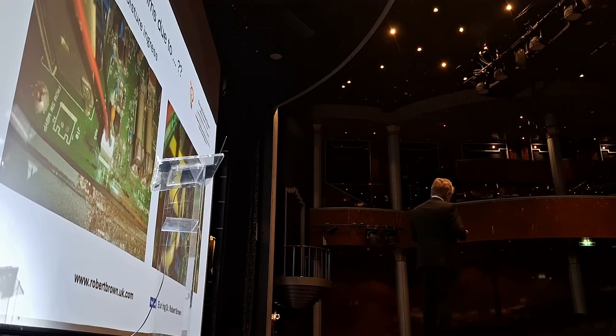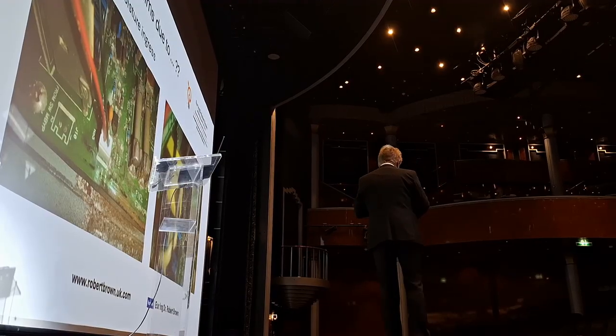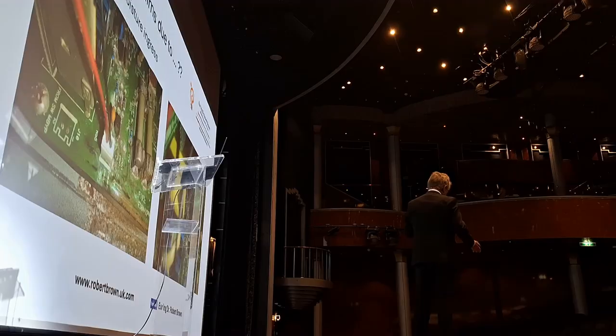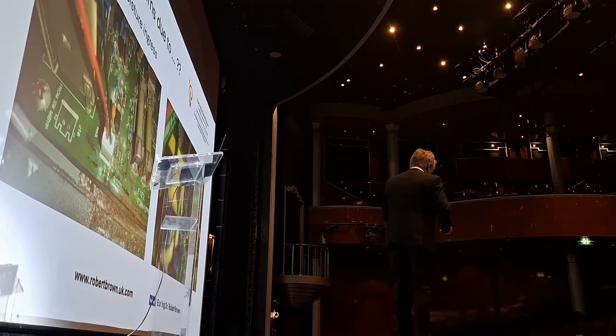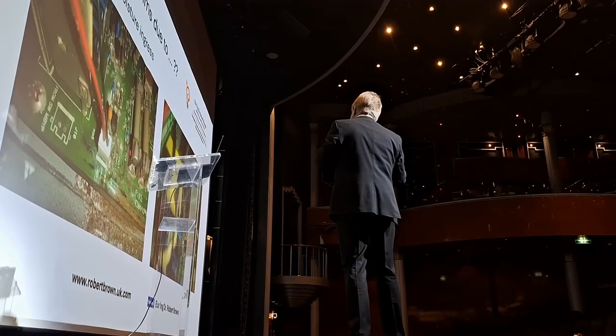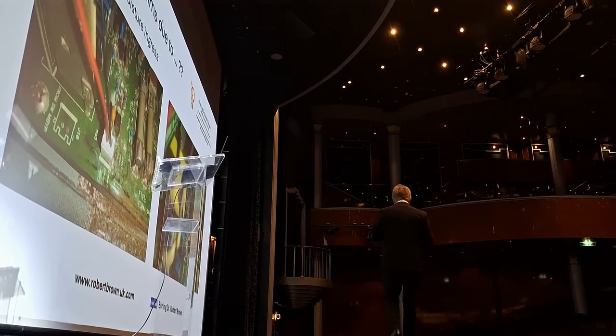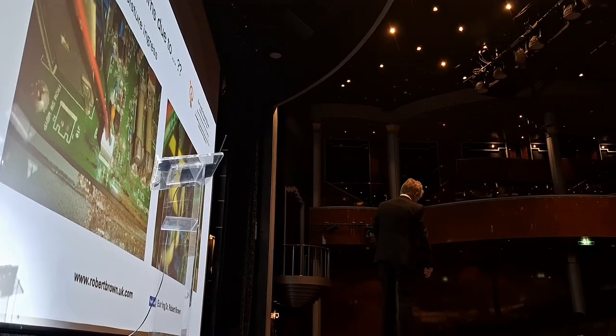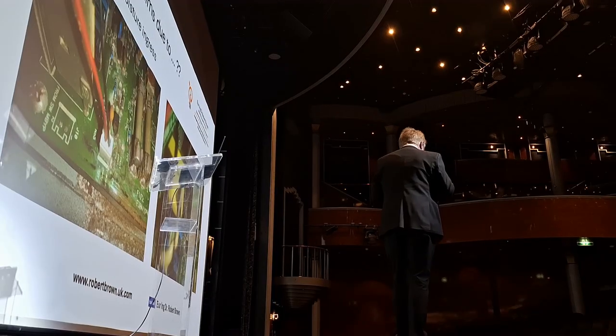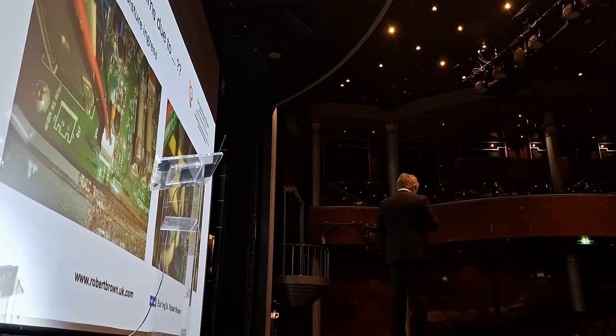This is an example of what I mean by accumulation of salts. I introduced in the first talk a circumstance where a water company deposited raw sewage onto a beach in southern England, and we were looking at the failure of a particular piece of equipment, a UPS system, uninterruptible power supply. And when we went inside it, and you looked at the circuit boards, you could see that some of the electronic components started to accumulate deposits. They were corroding, and the reason they were corroding is that the cooling air that was being drawn in had, one, moisture in it, and two, H2S, hydrogen sulfide. Hydrogen sulfide is a byproduct of the wastewater process.